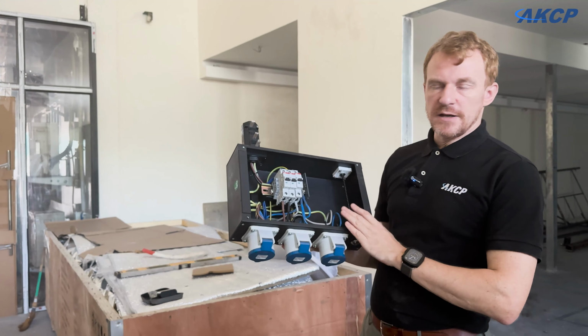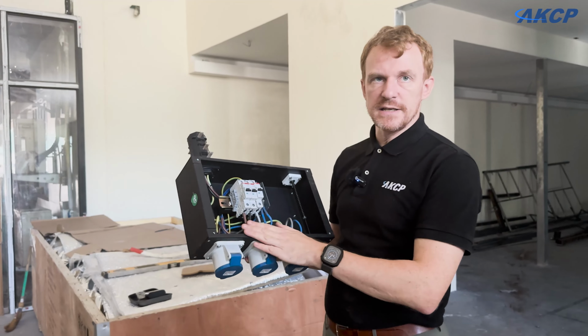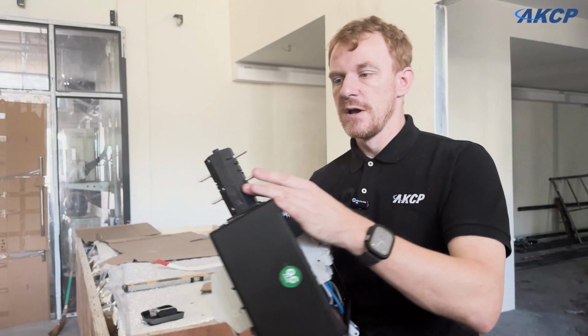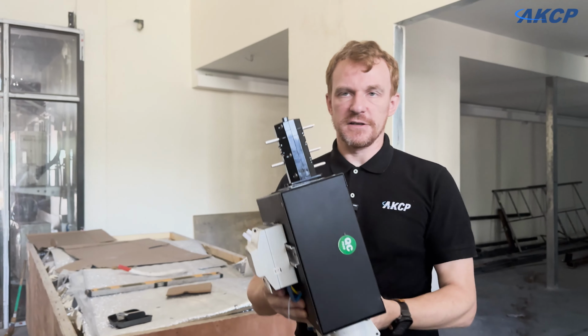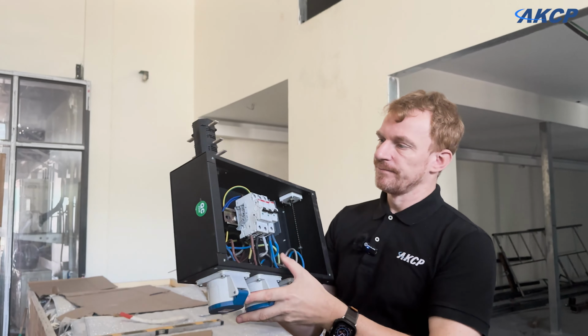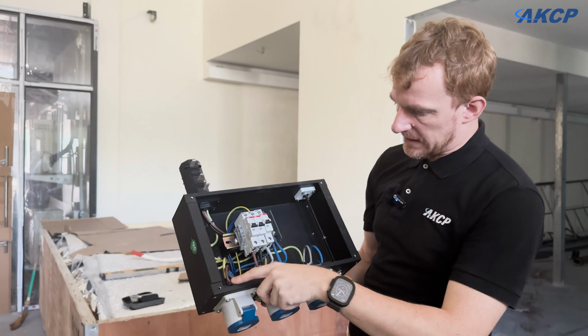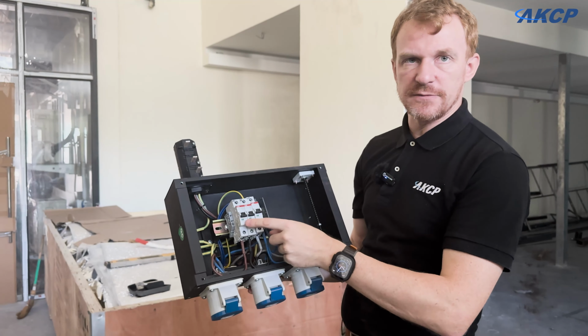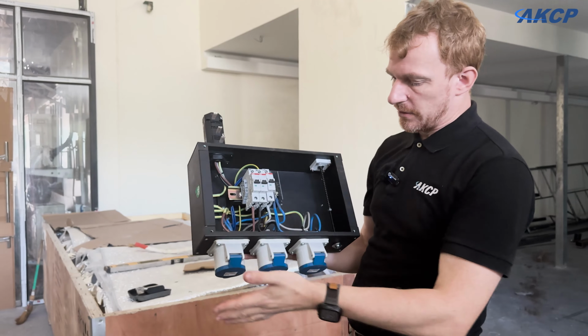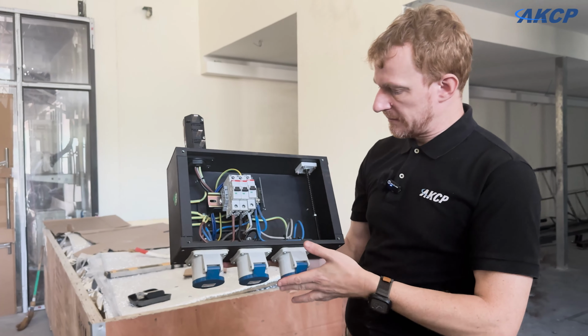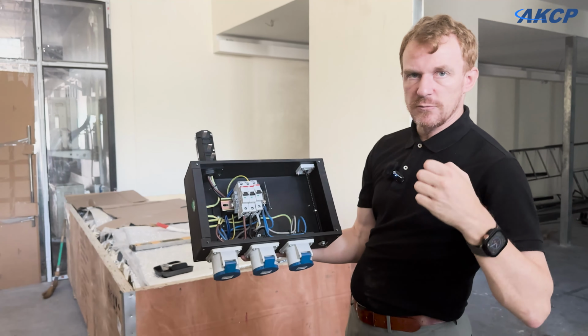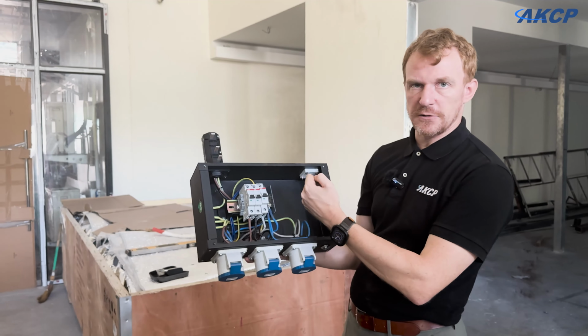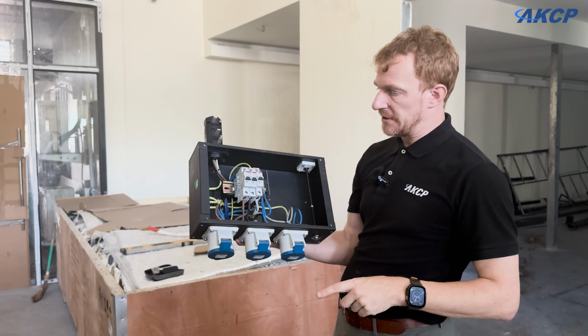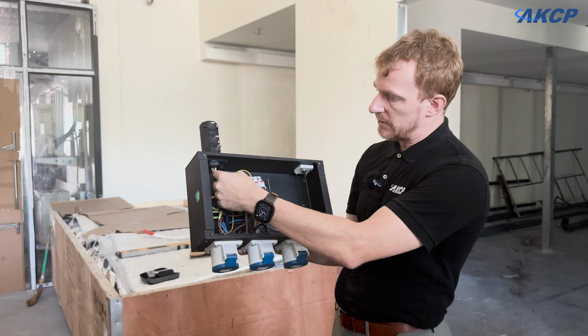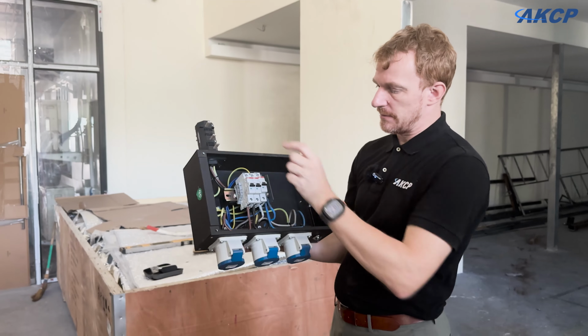This is the overhead breakout box that comes from the bus bars. So we have 3-phase coming in. This goes up and clips into the bus bar. The 3-phase coming in is split out into 3 individual phases with 3 20-amp breakers. On each one of these, we'll be putting one of those 3 heaters. On the front of this, then, we'll have one of those red 3-phase sockets, which the fans will be plugged into, and we'll tap that 3-phase power into the 3-phase, which is coming from here.